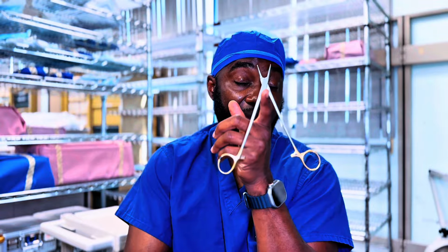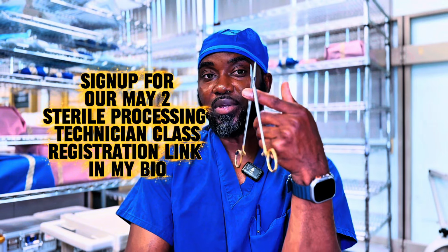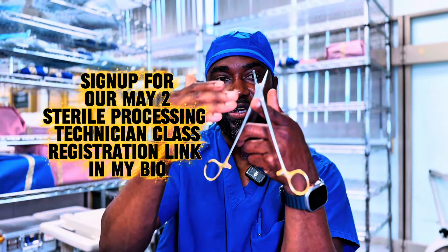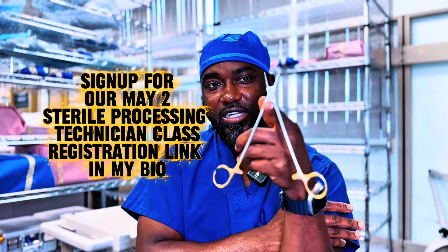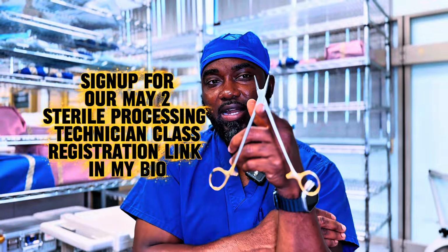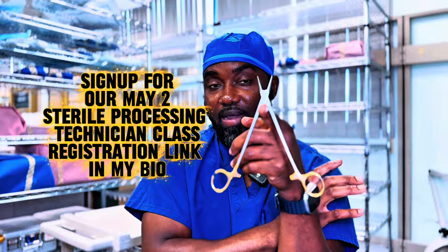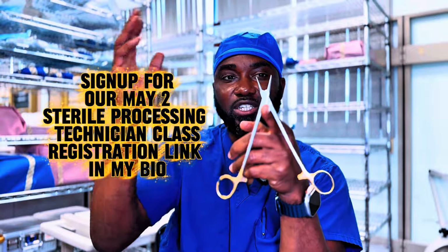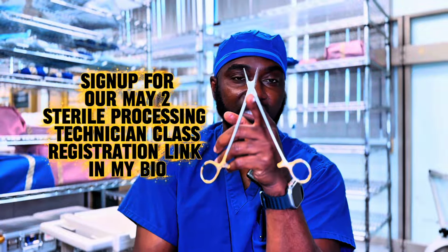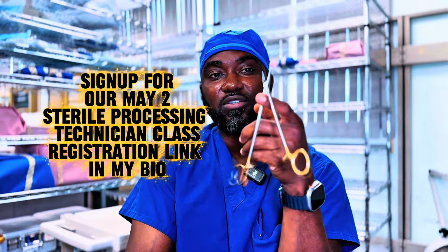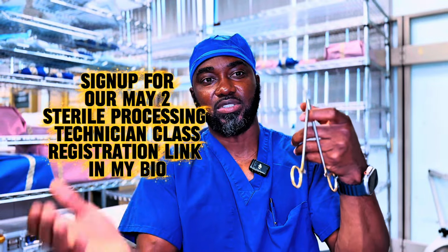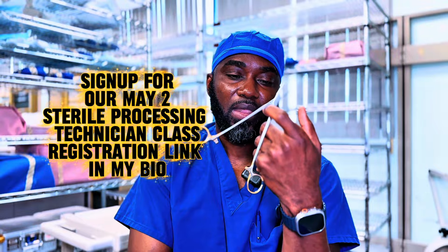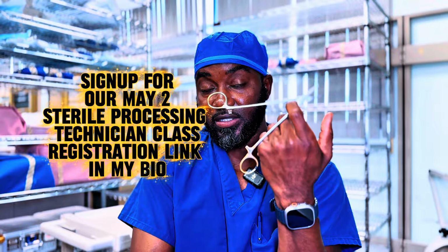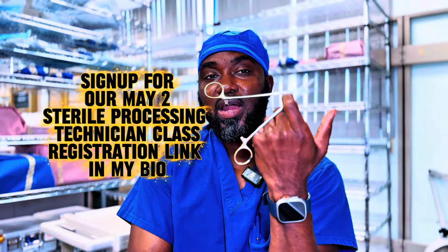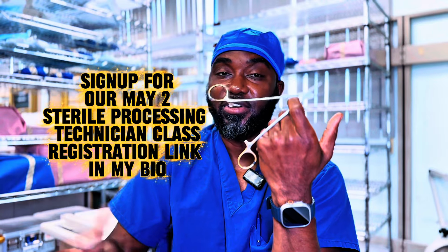What is done by the manufacturer in the lab to test these instruments at half cycle for 3 consecutive times to make sure that all microbial life forms on here are dead is the validation cycles. What this means in short is that manufacturers will validate medical devices, and send the information on to end users at hospitals, dental offices, and ambulatory care centers to verify the validation process that was carried out in an independent lab. When your manufacturer sends you instruments, they have validated the parameters they sent you to be verified by your facilities.